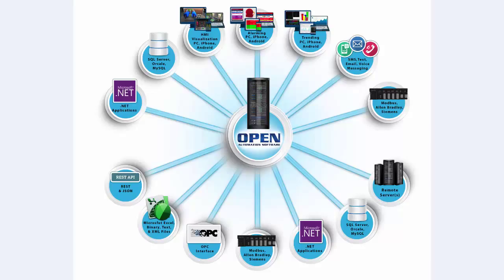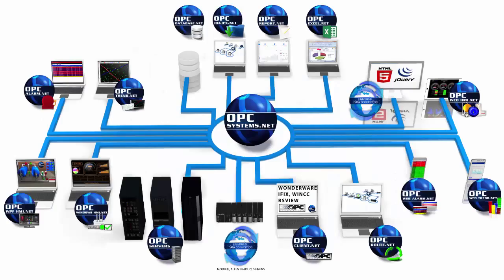And all of the data is openly accessible. That's one of the things that we pride ourselves on, that you'll be able to access the data openly. Even when we're logging to SQL Server, Oracle, or MySQL, the data will be in open format. We can even connect to third-party SCADA systems like Wonderware, iFix, WinCC, and Rockwell's RSView. With those applications, we can connect to them either as an OPC server or an OPC client.